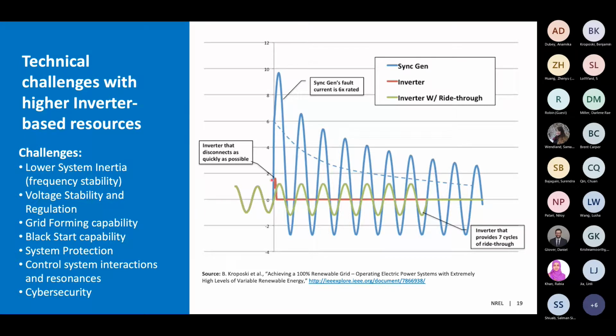That can be seen in this example, where if you had normal operations and then all of a sudden a fault, your synchronous generator potentially could provide a huge surge in fault current. Now, that particular characteristic allows us to look for this large surge and do what we call overcurrent protection. So we can measure very quickly, see this large fault current happening, and that tells us something is going wrong in the system, and we can start to use protective devices.